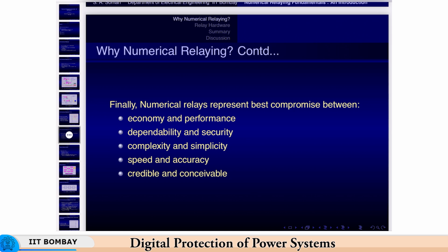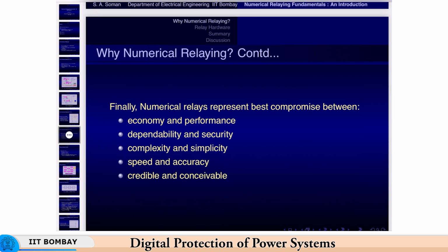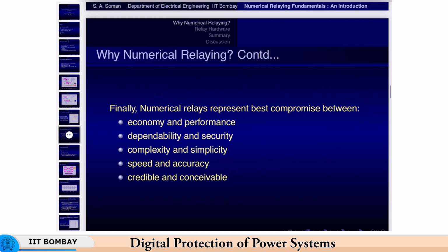One word of caution here is, just because they are numerical, we would assume any computer is faster, but in all applications numerical relays may not be faster than electromechanical relays. One example is a distance relay, where in a numerical relay you have to compute the phasors and then take the ratio and all that, whereas an analog electromechanical relay can directly do a V by I kind of calculation. So just because it is numerical does not automatically imply that it is a faster relay. That is one word of caution.